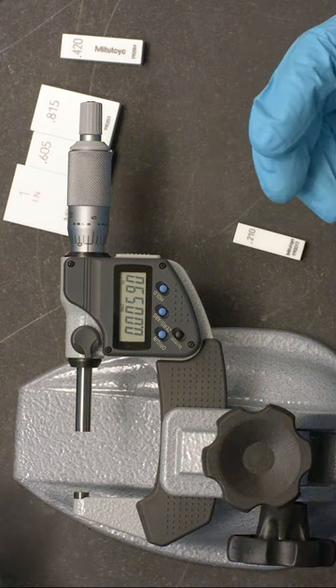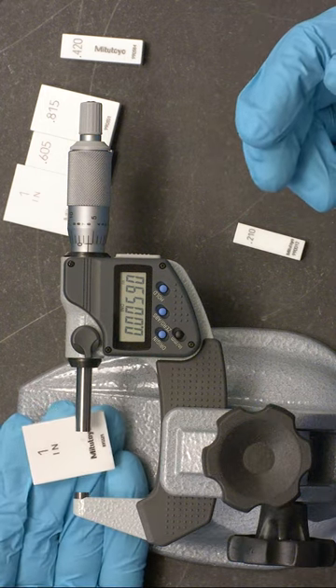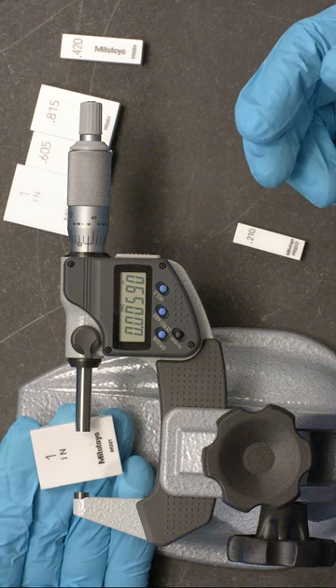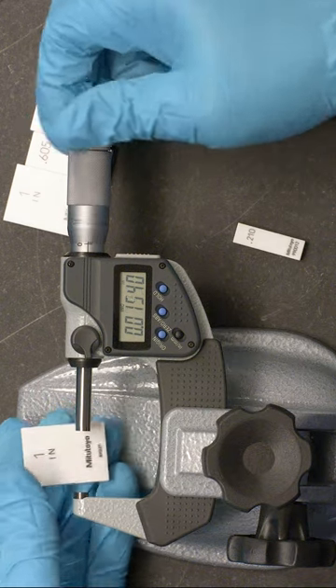Instead, you should use a gauge block. In this case, this 1 inch gauge block I'll use for this 1 to 2 inch micrometer.